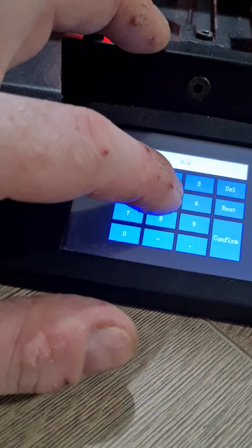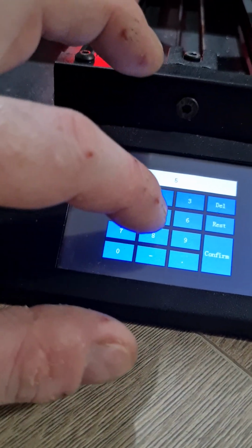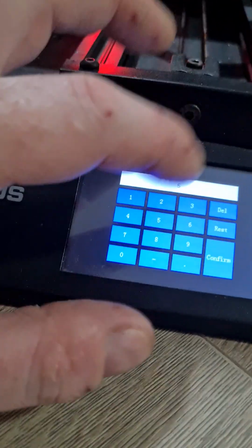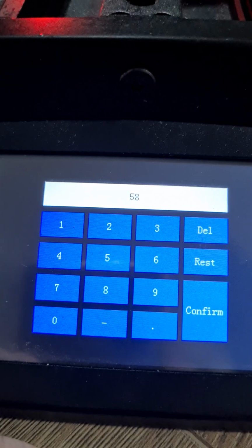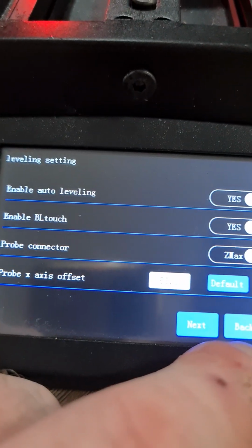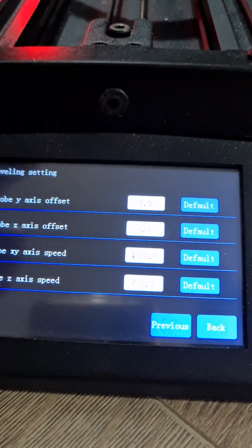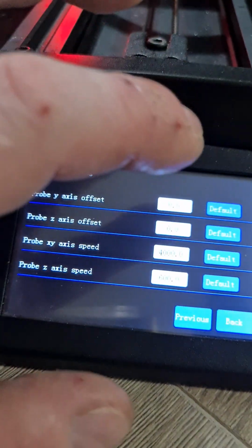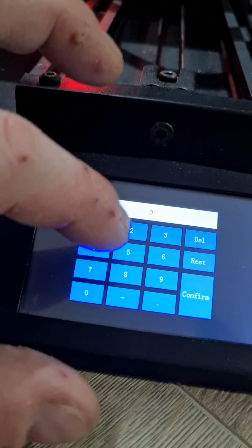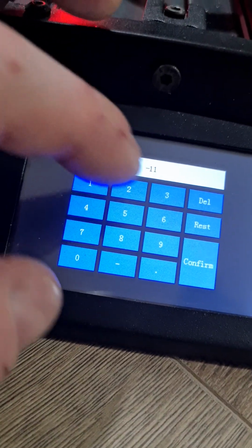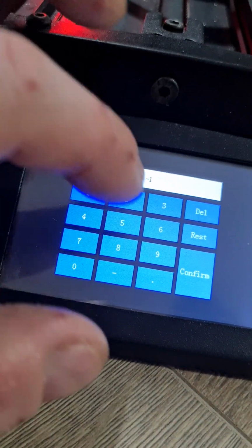So then now you'd enter your 58 for your reset, otherwise you're going to end up with 0 point whatever. 58, don't know if you can see that. Yep, confirm. Okay, next page. Y probe offset is reset, minus 15, confirm, back.